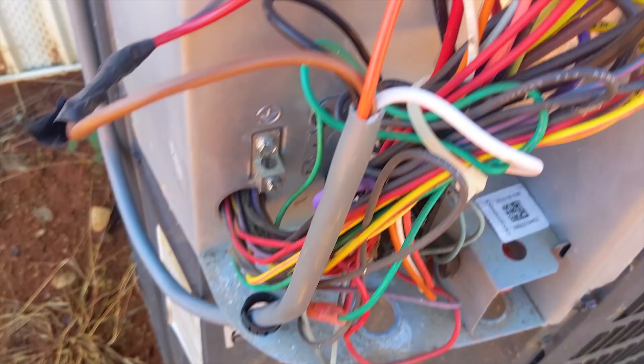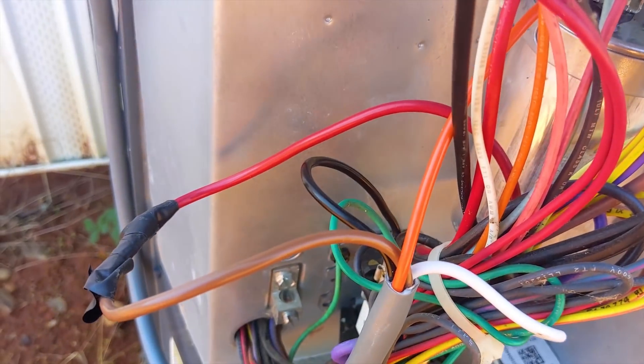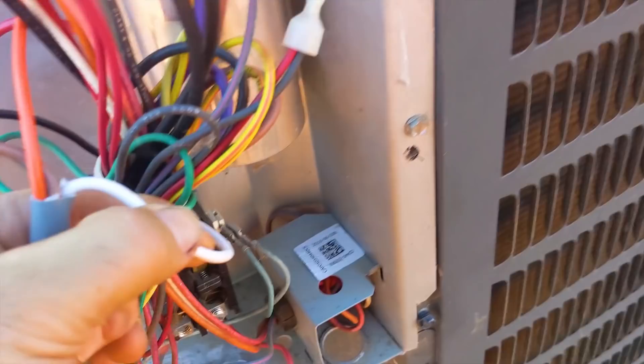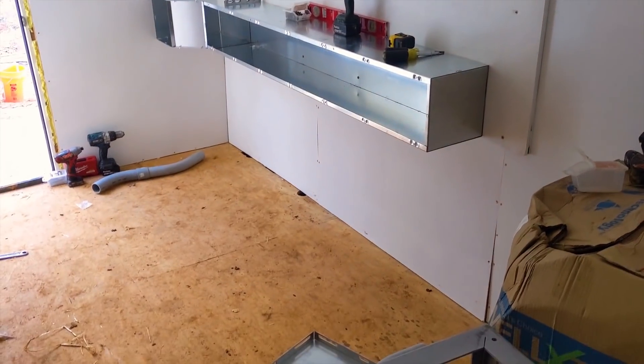We need to get up to the mech room. Not sure if this is wired in right — this is a Micro Air Easy Start. It looks like the hot wire is spliced to the brown wire on the Micro Air, the orange wire goes to the hermetic terminal on the capacitor, the red wire stays on the common, there's a purple wire, a white wire that comes down here to this contactor, and the black wire goes down on that terminal.